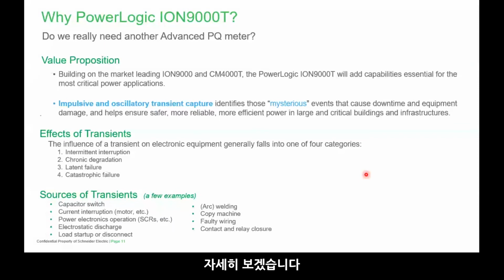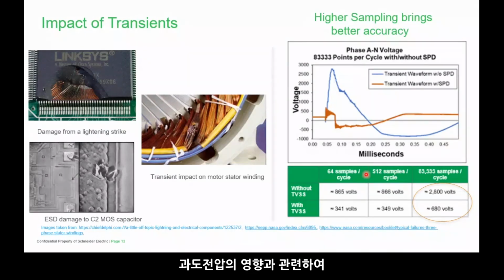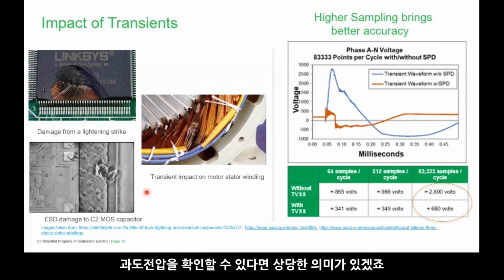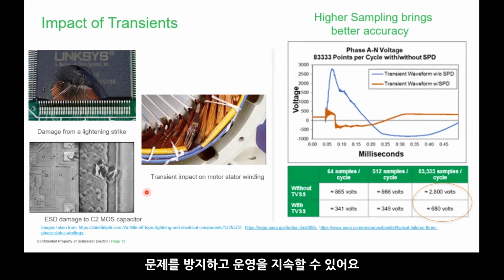So I'm going to cover a bit on this part. The impact of transient, maybe you've seen this picture before, is causing some motor winding to start to burn, as you can see from here. These are really damaging, because after a while you will find that your loads and your motors start to fail. You can also see damage caused by lightning, which damages electronic components. So these are basically the impact of transient. It's not easily visible, but once you are able to capture it, it's very meaningful, and you can avoid this and keep your operation running.